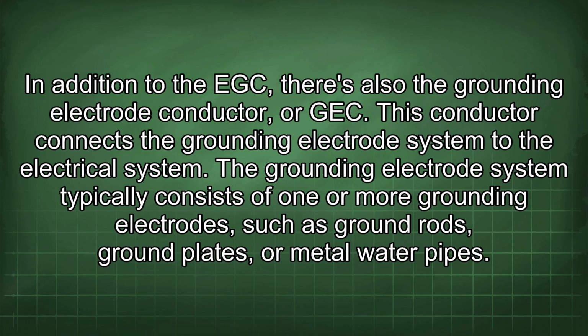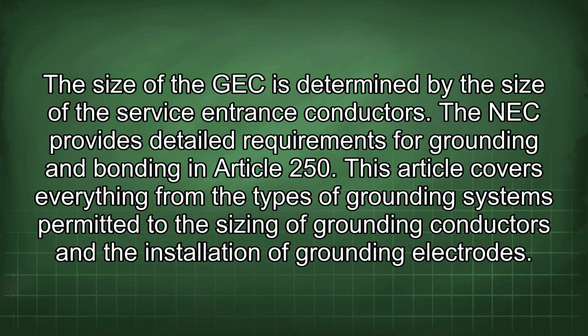In addition to the EGC, there is also the grounding electrode conductor, or GEC. This conductor connects the grounding electrode system to the electrical system. The grounding electrode system typically consists of one or more grounding electrodes such as ground rods, ground plates, or metal water pipes. The size of the GEC is determined by the size of the service entrance conductors.